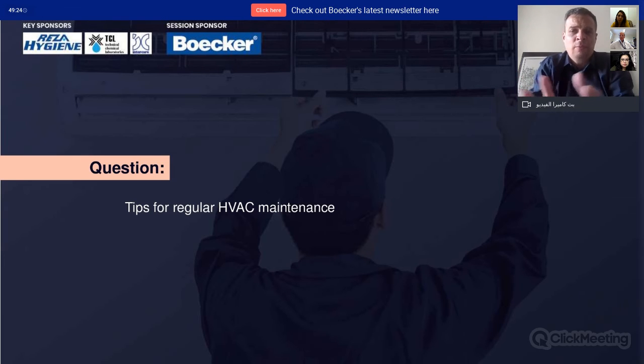Filters don't have to be replaced every two weeks. Wait until the pressure drop in the system is high enough, and the system should be able to tell you when that point is reached, so you can go and replace a dirty filter. But never wash them—replace them, buy a new one. Make sure you buy certified filters that fulfill the requirements and standards, and this is only ensured by a certified filter. Also check the certification pack with the certifying body to make sure it's still valid and not a fake or forged one.